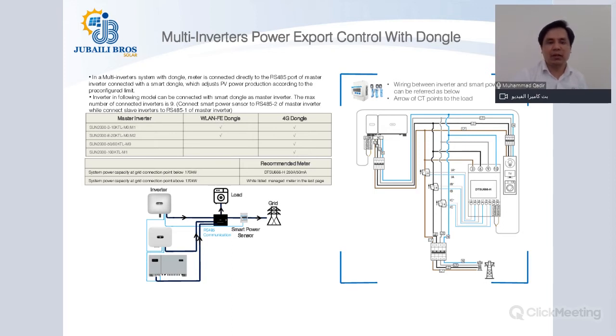Multiple inverter power output export control with dongle. Now, in case you have multiple solar inverters, the models could be different. So you must make sure that the inverter which is connected directly to the smart power sensor is compatible with that. In the previous table, or even on this screen as shown, these inverters could be, in case of a WLAN-FE, from 3 to 20 kilowatt, to which you can connect your smart power sensor, thus making any of those 3 to 20 kilowatt sizes a master inverter in your PV plant, and making the rest of the inverter models slave inverters.